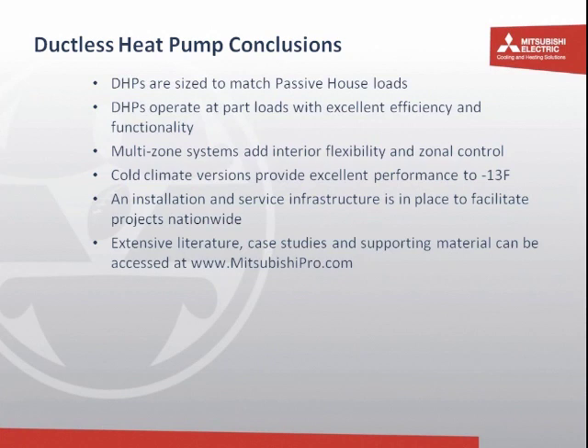Second question was, do low-profile ducted units meet the same efficiency as the mini-split units? And I suspect what this questioner means is, do they meet the same efficiency as the wall-mounted units, which is the more traditional mini-split indoor unit? They don't quite match up because the ducted unit actually does require a bit more energy to overcome the resistance of the ductwork.